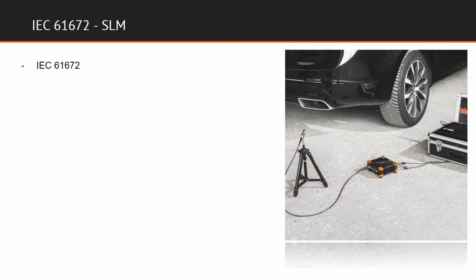As we have established the meaning and importance of performing the calibration itself, let's focus next on particular calibration procedures and their corresponding standards. We will begin with one of the most widely used and performed calibration services, which is Class 1 SLM calibration of our entire measurement chain according to IEC 61672. When it comes to sound level meters, IEC 61672 is actually the most widely used standard to perform the calibration.